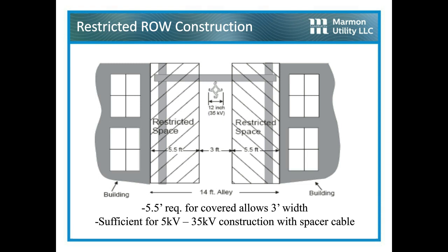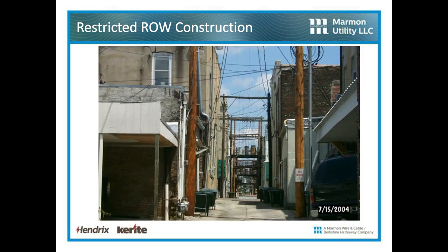And that's, while it's doable, 14 feet above the rooftop creates safety hazards for painters and workmen, working personnel on those roofs. So you can fit a spacer cable system here very nicely, save a bundle of money, and be NESC compliant. And this is the type of projects we're doing. There's the 15 kV rat's nest, if you will.